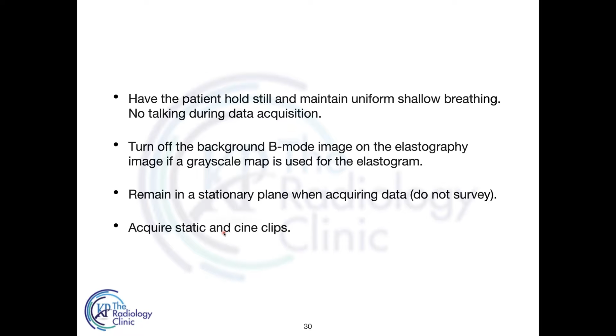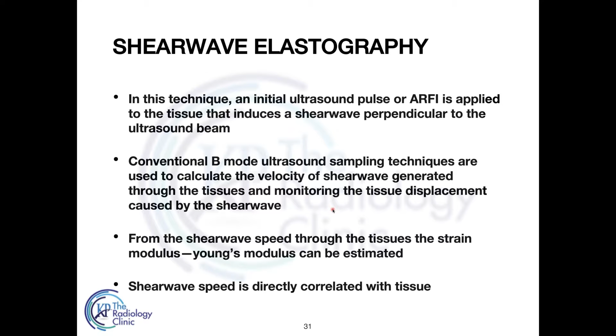Coming to shear wave elastography. In this technique, an initial ultrasound pulse or ARFI is applied to the tissue, which induces a shear wave perpendicular to the ultrasound beam. Conventional B-mode ultrasound sampling techniques are used to calculate the velocity of the shear wave generated through the tissues and to monitor the tissue displacement caused by the shear wave. From shear wave speed through the tissues, the Young's modulus can be calculated. The shear wave speed is directly correlated with the tissue stiffness.